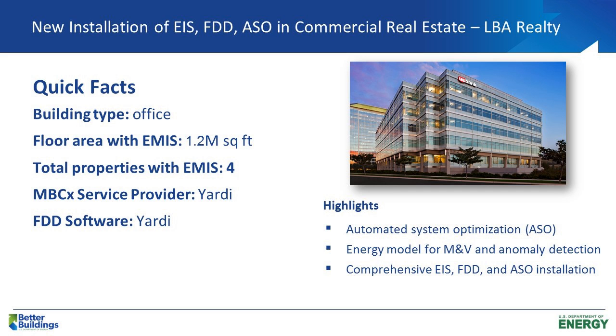They're going to tell us more about this automated system optimization process, but they really feel that supervisory control, continuously altering set points in real time without needing to interact with the tool the way you do with FDD when a fault is flagged, gives them good value out of the ASO.